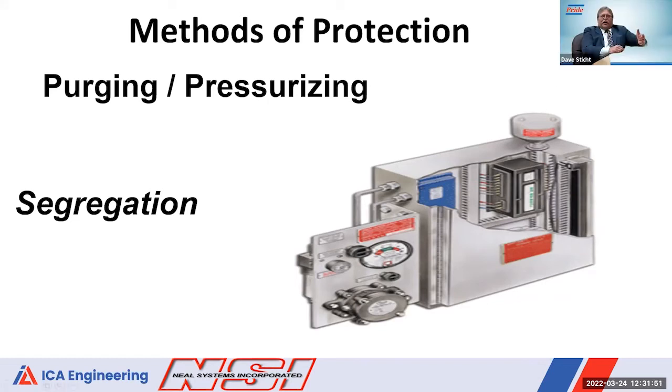And then you have your main electronics, your 220 or whatever the high voltage is. That's an explosion proof metal contained area. This is a NEMA-4 enclosure with pressurization inside. So they kind of work hand in hand. Sometimes it's just not possible to use another form of explosion protection, so purge comes in when you're dealing with high power drives or motors, or even some sampling systems and analyzer systems, where by the nature of the design you've got an internal source of release potentially in the panel, because you're bringing in a sample from the process. So you need to maintain that positive pressure inside to make sure there's not a flammable gas air mixture in there for an explosion to happen.